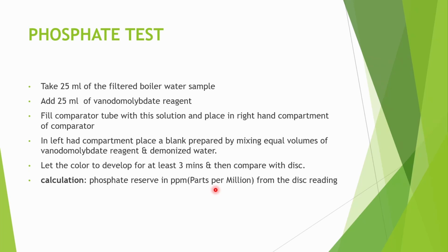So I have explained this because recently they were frequently asking about the phosphate hideout phenomenon. So hideout is the phenomenon of the phosphate ion concentration in the boiler water undergoing changes due to the fluctuation in boiler load and pressure, and this is called hideout.